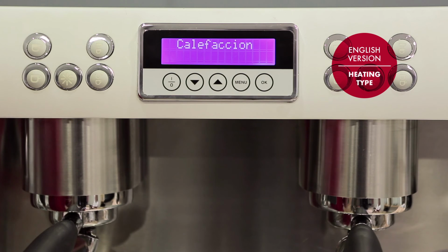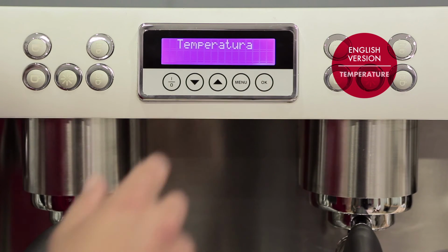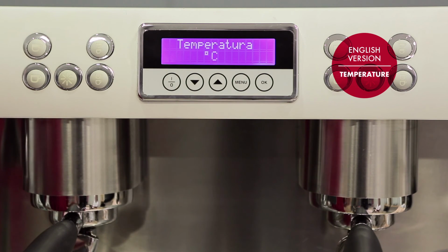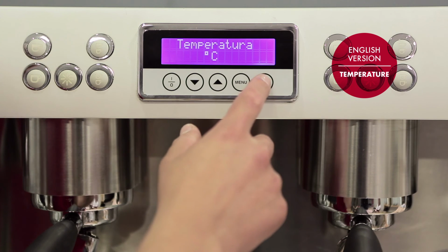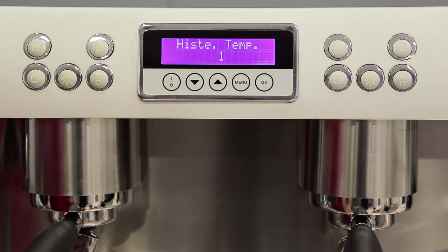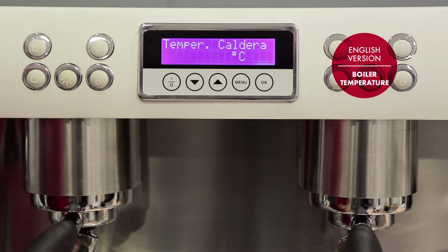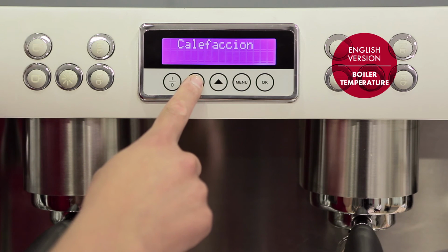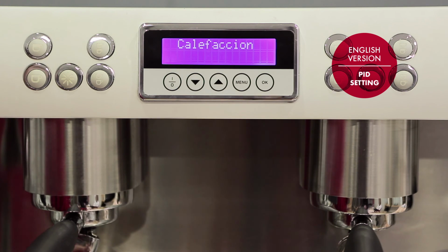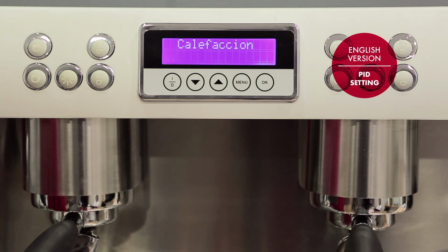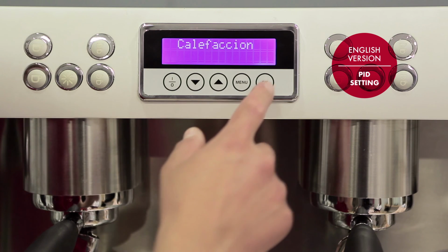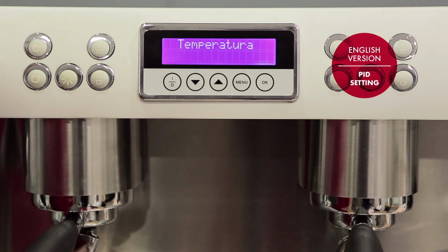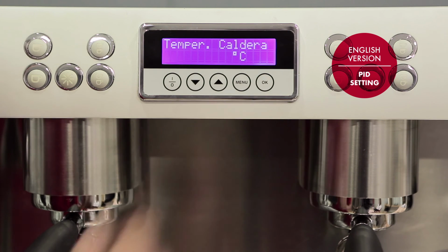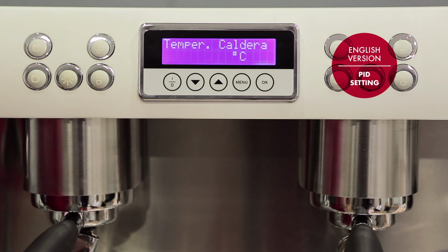If we select the option on-off, we press the OK button and choose the temperature units, Celsius or Fahrenheit. Afterwards, we select the gap within which we want the temperature to stay. The other option that we can select if our machine works with a temperature probe is the PID option. To select this option, we confirm with the OK button, select the temperature units, as previously explained, and select the temperature we wish the boiler to remain at.